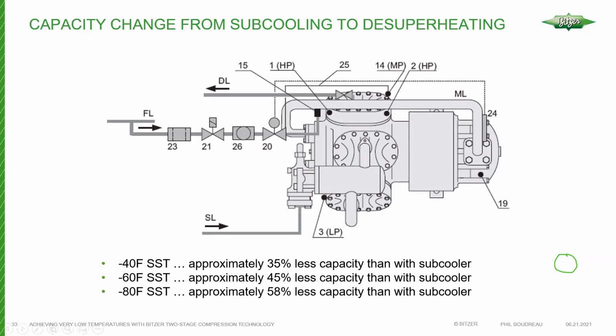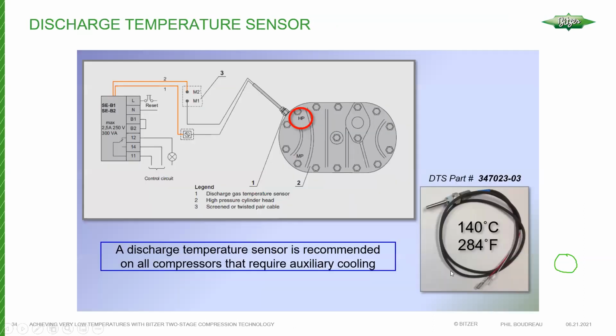This slide just gives you an idea of approximately how much capacity drops when you shut the subcooler off and go to a desuperheating mode. In the case of minus 40 Fahrenheit saturated suction temperature, it's 35%. At minus 80, on the other hand, it's close to 60%. These are major changes in capacity, so you can't be just switching modes back and forth. Generally, we don't recommend it. It can be done, but as I said, it's best to consult with BITZER.